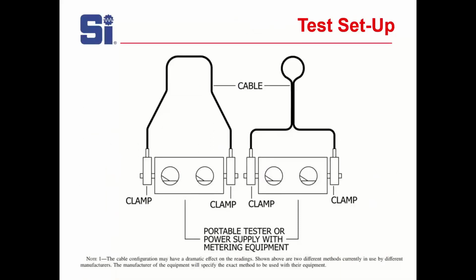And this is a ground tester. The different manufacturers have slightly different ground testers. But the fact of the matter is that how they tell you to run the tester may be different. And here you can see they tell you to put one more or less in a loop. The other one, they tell you to tie the sides together and then make a loop. They have their own requirements for testing. So just using it is not adequate. Use it in the way that is specified. And that, my friends, is how you ground something.